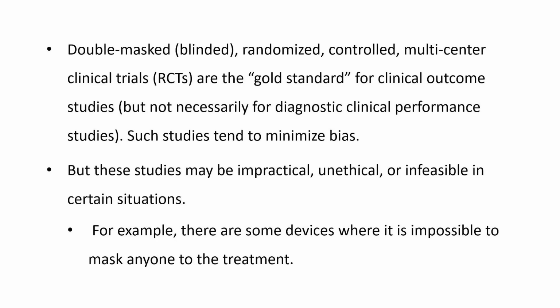Double masked or blinded randomized controlled multi-center clinical trials, or the RCTs, right? RCTs are the gold standard for clinical outcome studies, but not necessarily for diagnostic clinical performance studies, right? Such studies tend to minimize bias. Randomized controlled trials are pretty much good with the bias. They have low bias and variance. But these studies may be impractical, unethical, and unfeasible in certain situations. For example, there are some devices where it is impossible to mask anyone in the treatment, right?